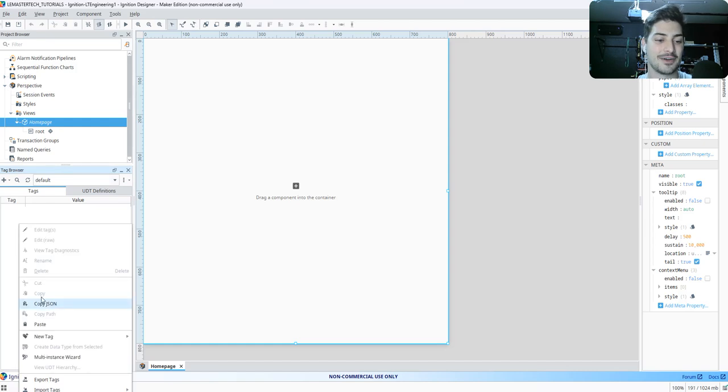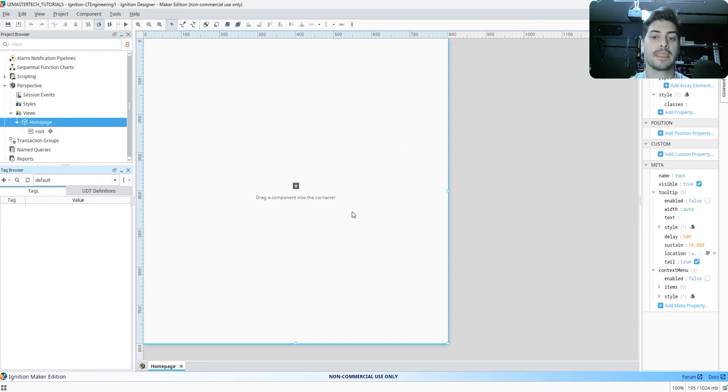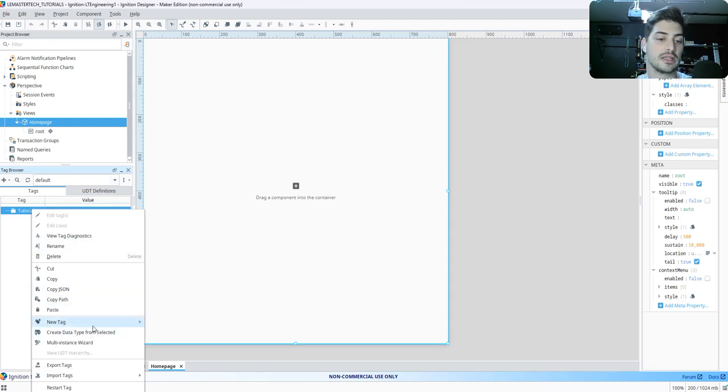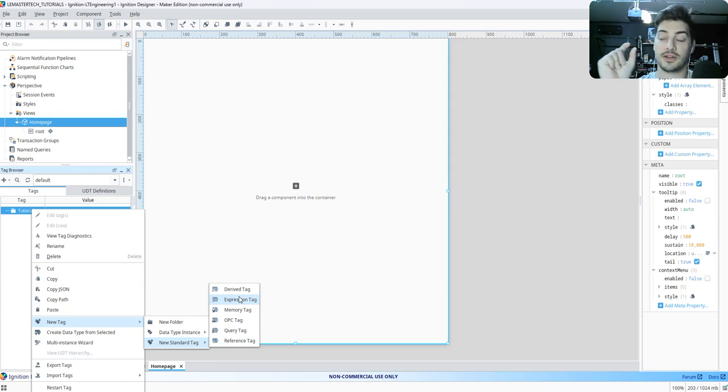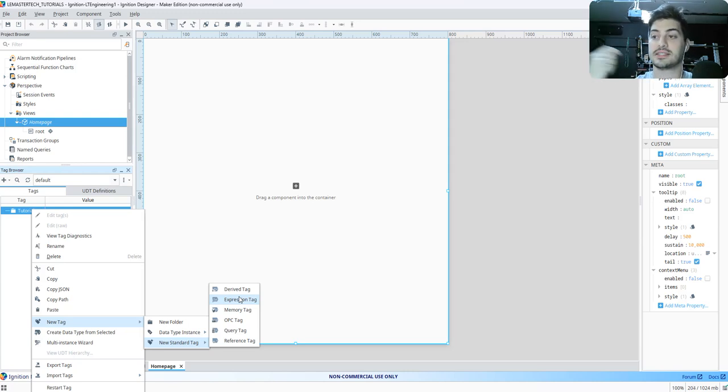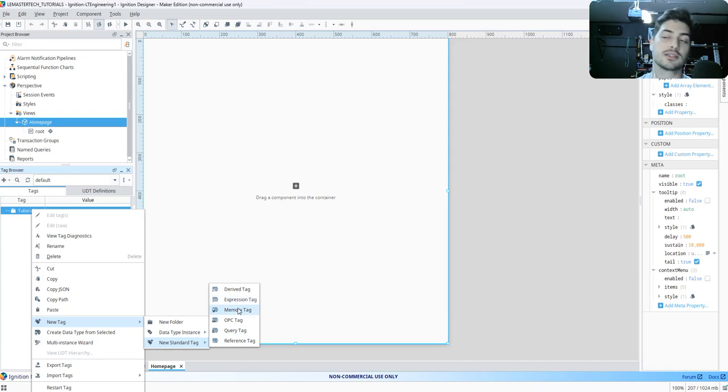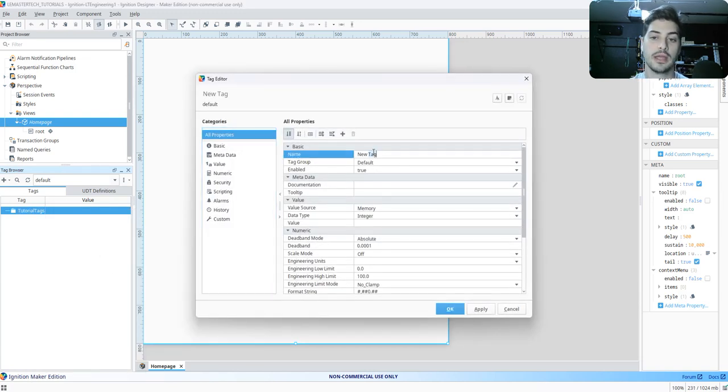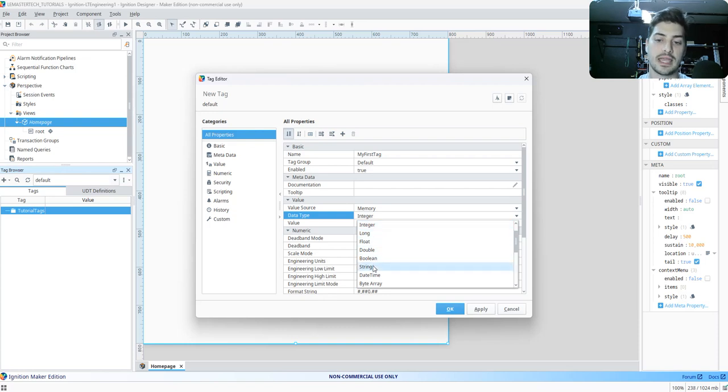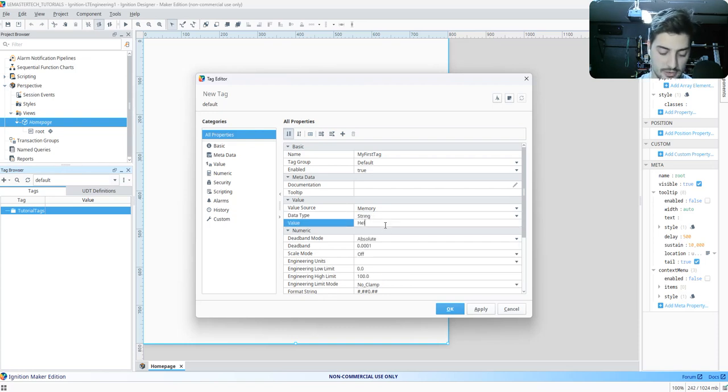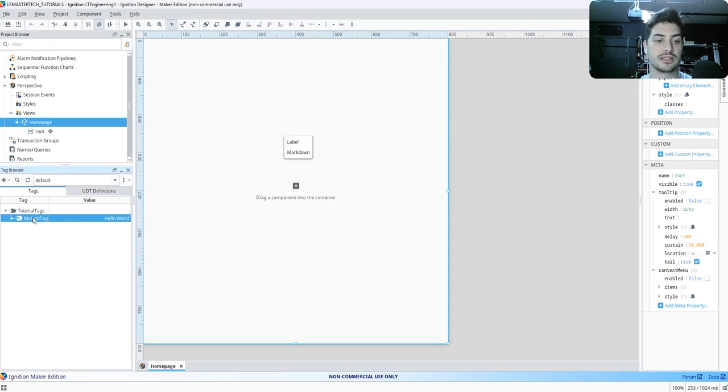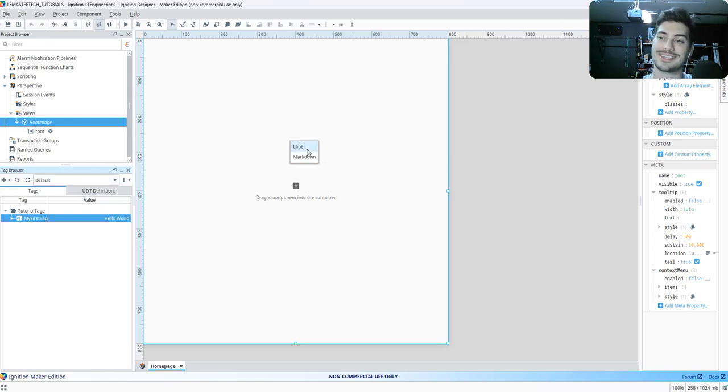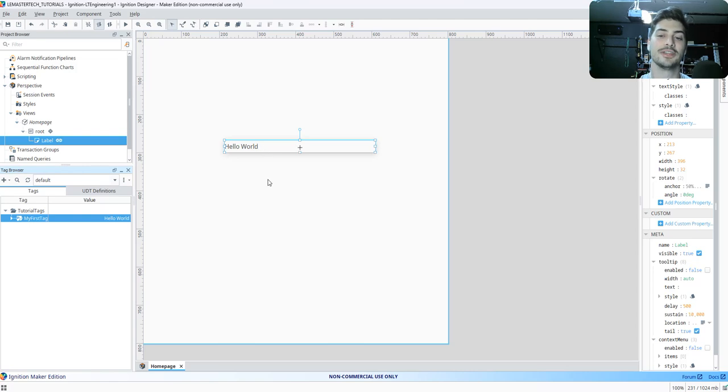So simplest thing I can do to show you guys like what Ignition is, is make a tag. So I think what I want to do here is I want to make a folder and I'll call this folder tutorial tags. And SCADA's and PLC's and basically anything automation and controls really live off of the tag structure, which is just having—in conventional programming, you'd think of it as a variable. In automation and SCADA software, it's a tag. It warehouses a tiny bit of data. It can be used for reading, writing, and logic. So let's go ahead and make a memory tag, which means it just lives on Ignition, it lives on this computer. And we will call it 'my first tag.' And let's make this a string. And let's give it an initial value of, why not, Hello World. Okay. And let's go ahead and drag my first tag onto the screen. And all we do is click on that tag and drag it onto the screen. And it's going to give us its top recommendations for what that data format might be. And so we'll hit Label.